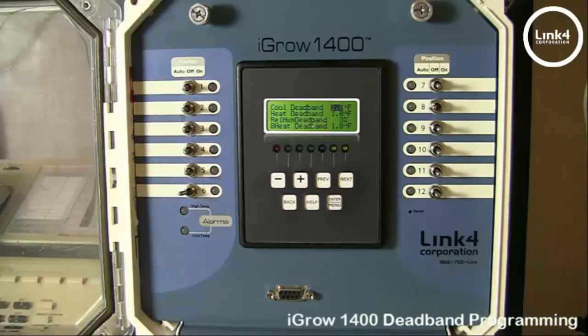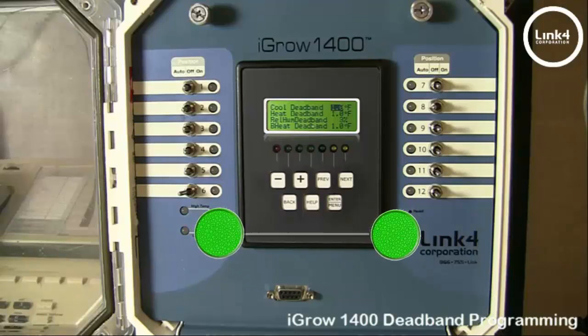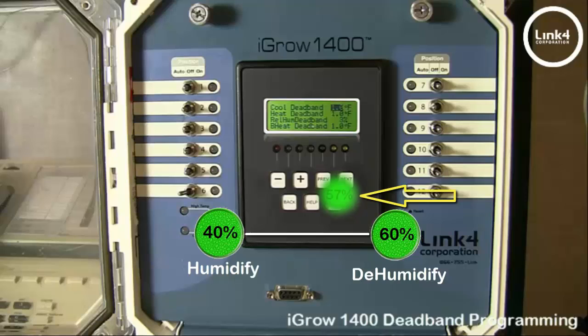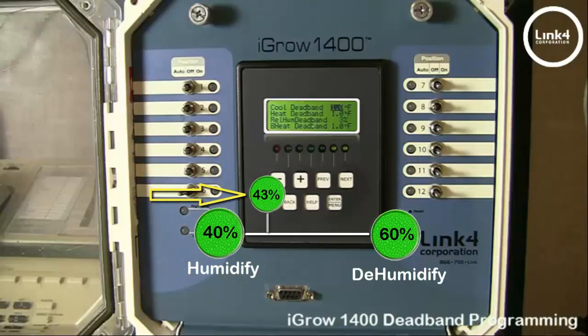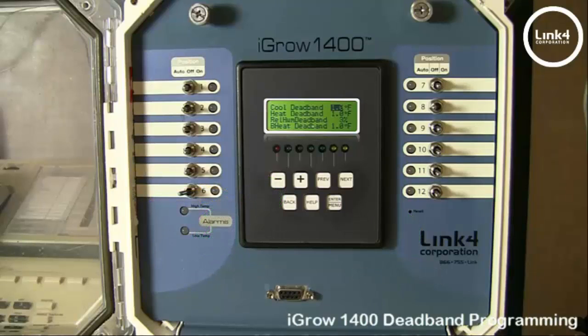Relative humidity deadband, this is the relative humidity percentage. The humidity must drop below the dehumidification threshold before exiting the dehumidification state. It also is the relative humidity percentage. The humidity must rise above the humidification threshold before exiting the humidification state.